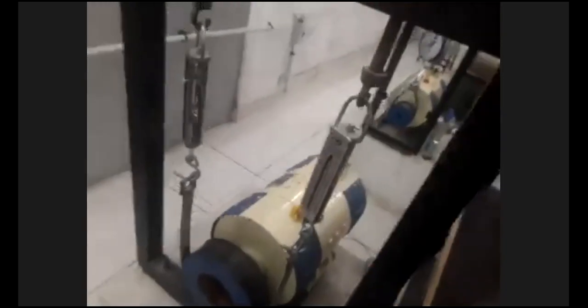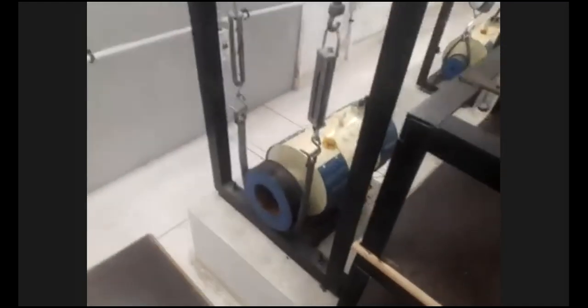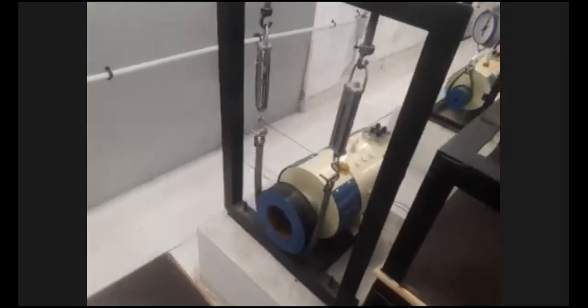But while performing these types of tests, precaution should be taken, because applying the brake or blocking of the rotor may cause damage to the motor. And there is a starting panel, that is a 3-point starter, which is necessary for this.